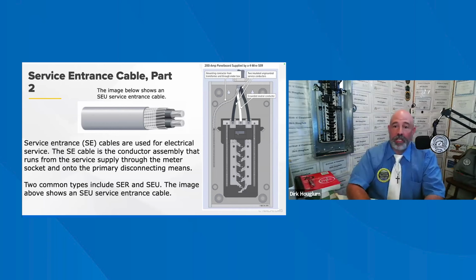The SER cable is a 4-wire round service cable with 2 hots, a neutral and a grounding conductor. It's used after the service disconnect, such as for feeder panels or sub panels, since it includes both neutral and ground. Inspectors should know the common cable size, wire types, copper or aluminum, and their amp rating.